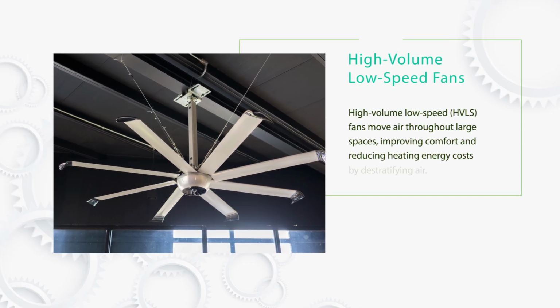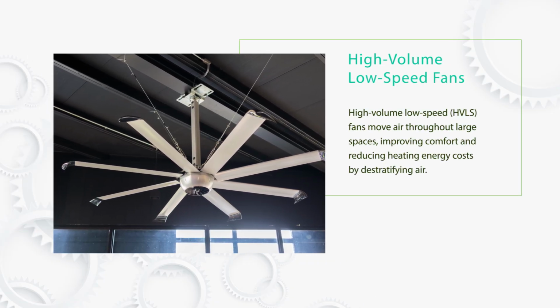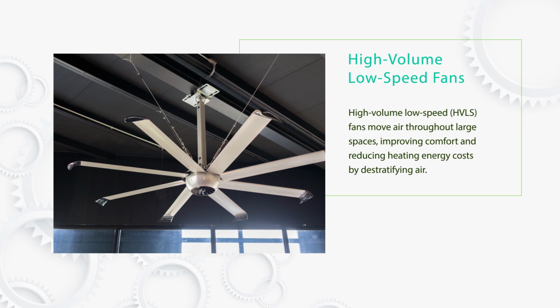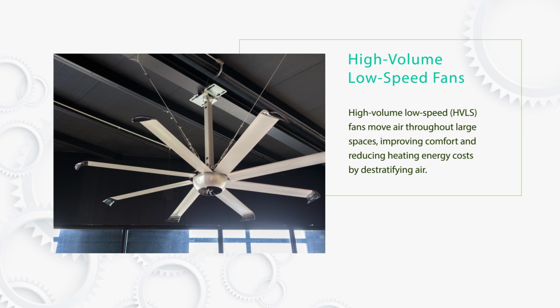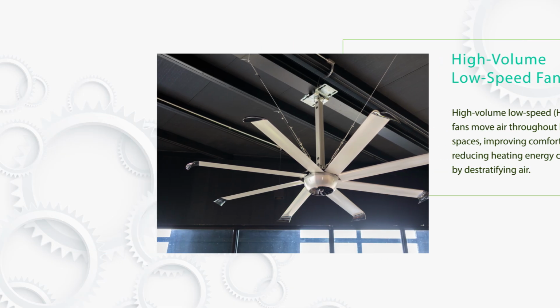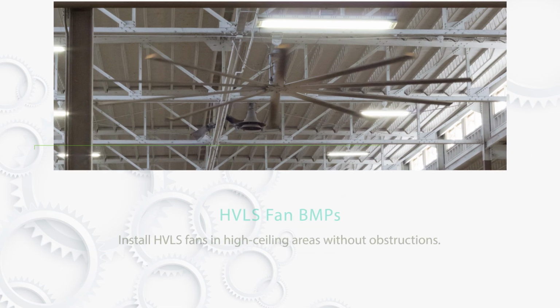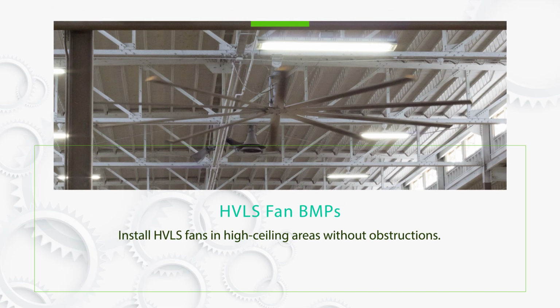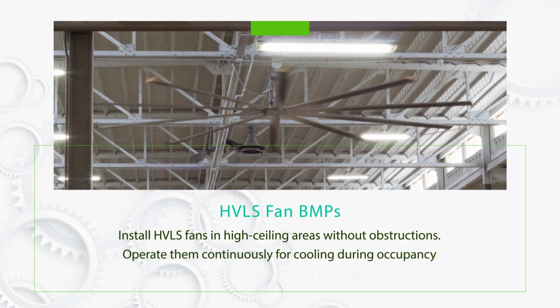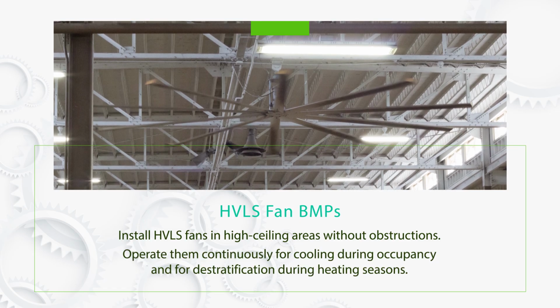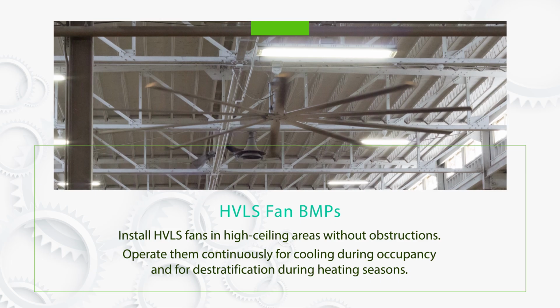High-volume, low-speed HVLS fans move air throughout large spaces, improving comfort and reducing heating energy costs by destratifying air. Install HVLS fans in high ceiling areas without obstructions. Operate them continuously for cooling during occupancy and for destratification during heating seasons.